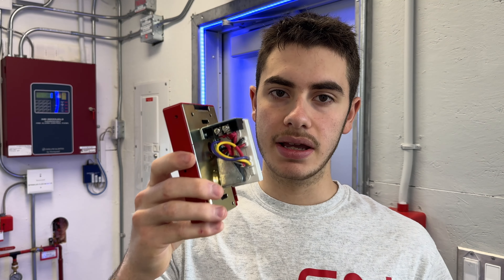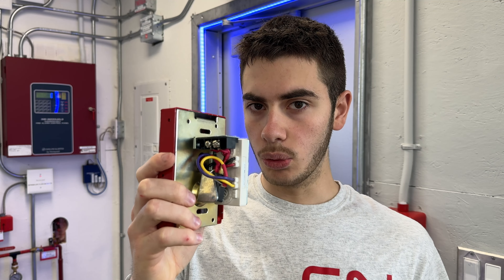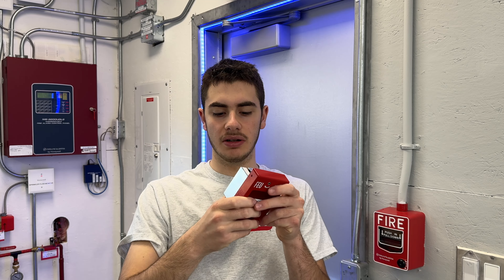I was able to take this one home and I'm going to see if I can fix it up, or see what's wrong with it. This is an addressable pull station, so we have an addressable module on it — actually just a mini module, a Notifier FMM-101A. It's just a monitor module, and because of that these program differently than an NBG-12LX. This shows up as mini module or monitor module, a little bit differently.